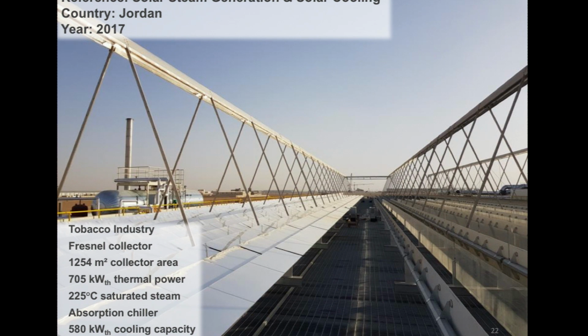At this system, we have realized a combination of heat and cold, as the production is not operating 7 days a week, but only 5 or 6. They can use the heat to power an absorption chiller, and the cold - there's always need for cold, even on the weekends. An absorption chiller is basically a machine which converts heat to cold.